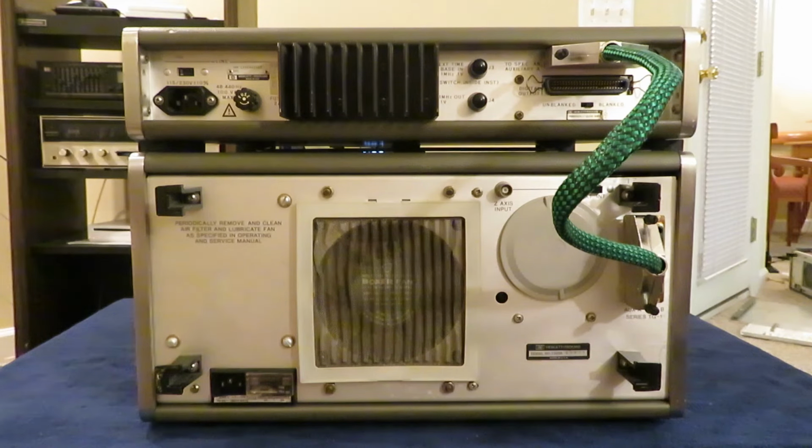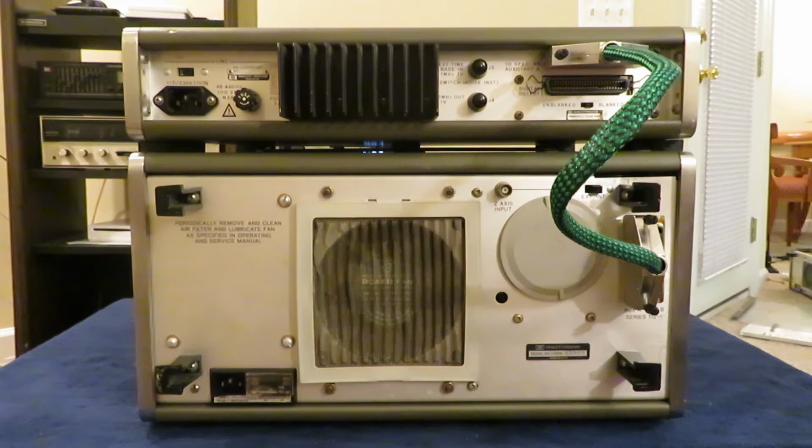Now that we've demonstrated some of the functionality of the 8443, I wanted to talk a little bit about what it takes to get one of these working, because on the 8443 tracking generator and the 8445 pre-selector, there is a very big catch. And the catch comes in the form of this cable right here. In order for the add-on box to be able to know where along the sweep the spectrum analyzer is, it needs to be able to talk to the internal functions of the spectrum analyzer. And it does so by way of this cable.